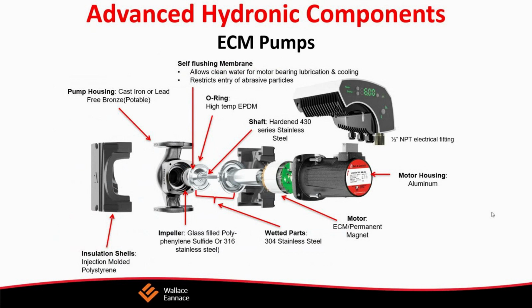These large wet rotor pumps are high performance pumps. They take efficiency to advanced levels. They use ECM permanent magnet technology. They feature state-of-the-art hydraulics and advanced motor design and truly intelligent controls. They have a display. You can actually read the flows and head.